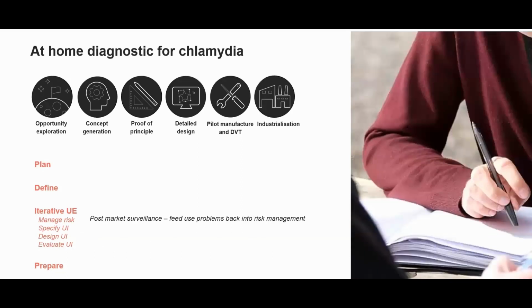So moving into the final stage of development, commercialization, there is still a responsibility for manufacturers to conduct usability engineering activities in the form of post-market surveillance. So this is about monitoring customer complaints and making sure that if there are any known or publicly reported use-related risks or usability issues that have been identified with your product, these need to be fed back into the risk management process, and you may need to do some further optimization. So hopefully this gives you a better feel for how you can apply usability engineering as part of a development process for this particular application, which is a diagnostic for chlamydia.